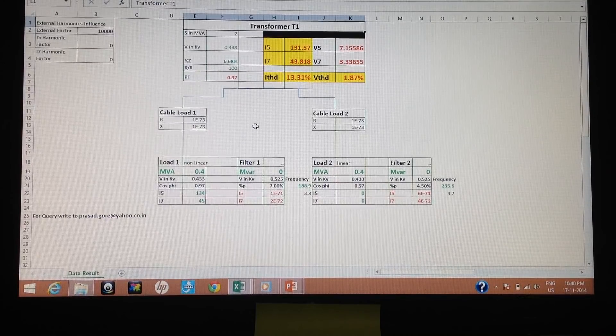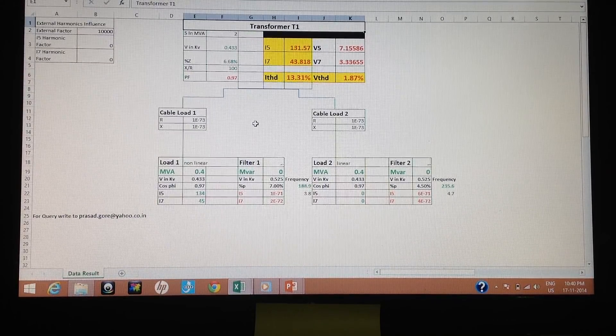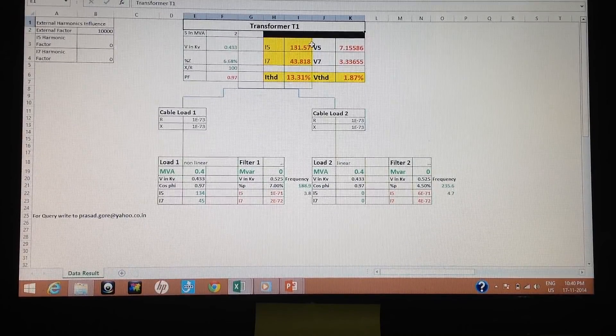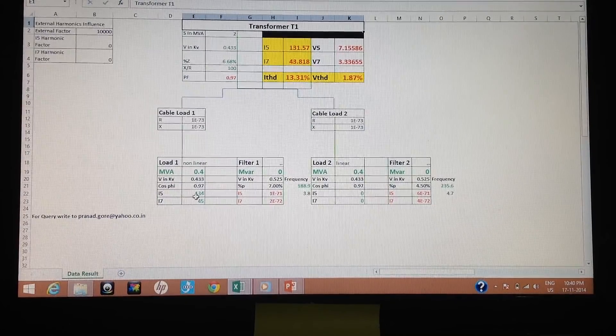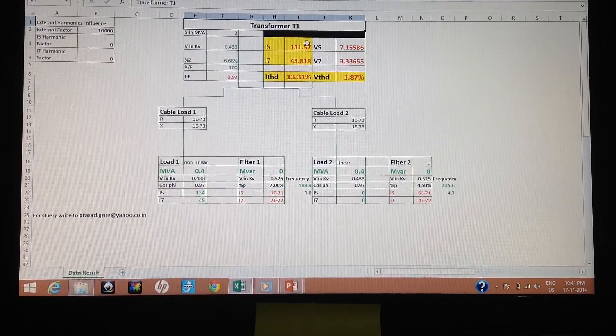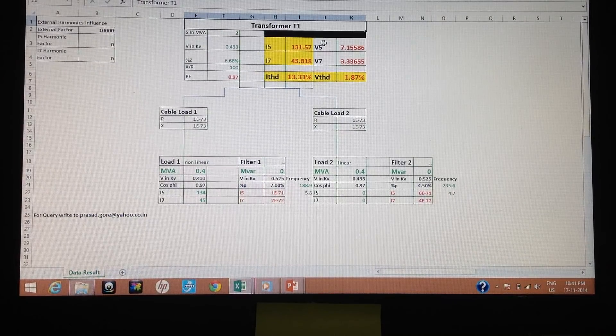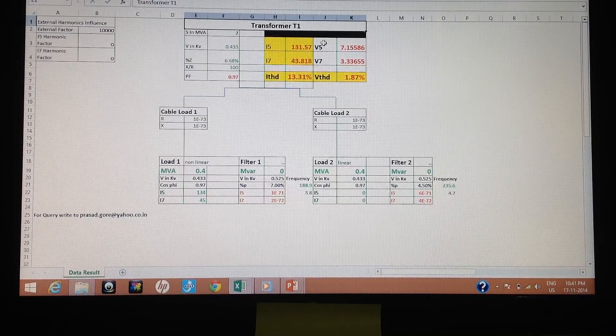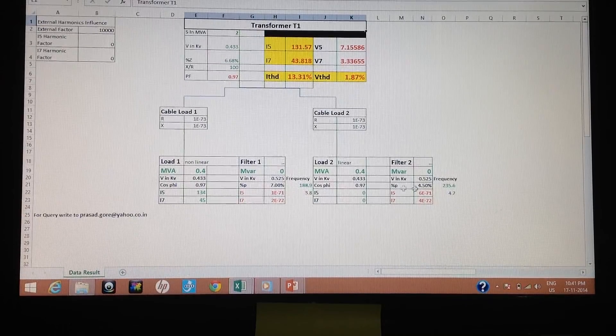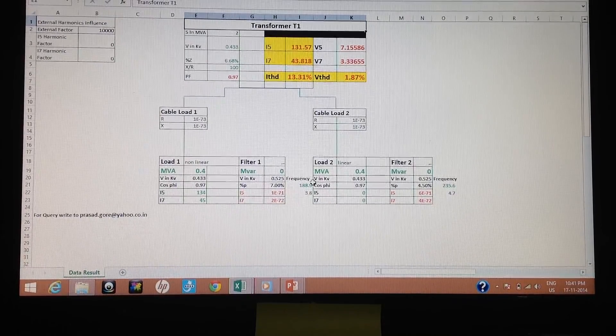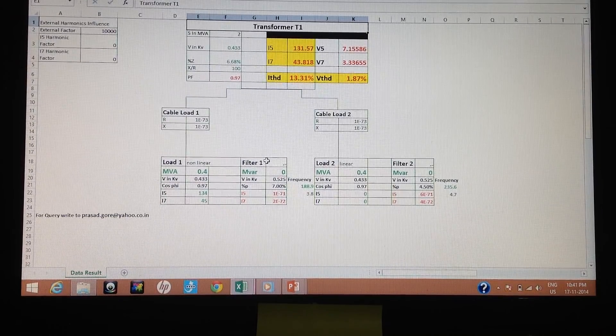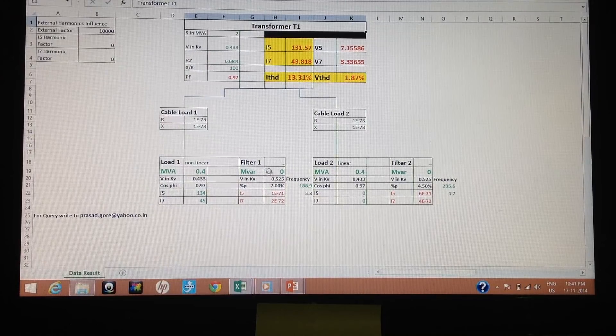You can see that I5 and I7 are getting reflected at the transformer mains, but not with the same amplitude, because there are several factors affecting the final observed harmonic values at transformer mains. Now I will simulate some situations: what happens when we put a 7% harmonic filter, what happens with a 4.5% or 235 Hz frequency filter, and what happens when we use single-tuned harmonic filters for multiple frequencies. Let's start the simulation.